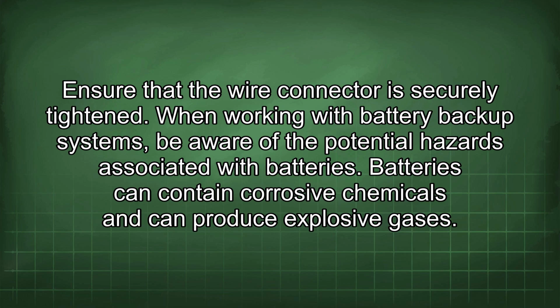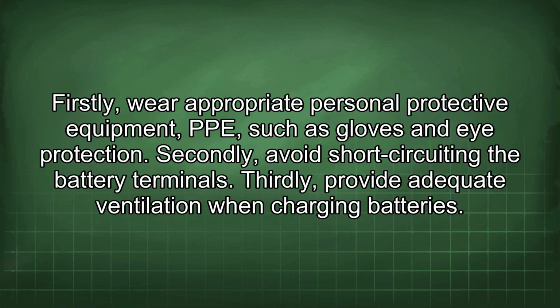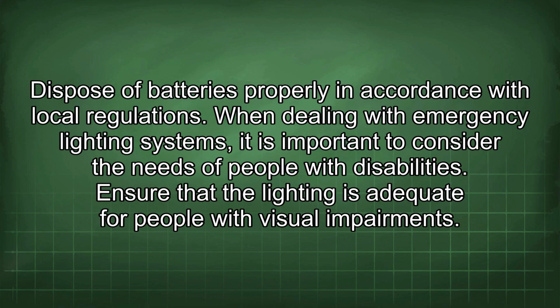When working with battery backup systems, be aware of the potential hazards associated with batteries. Batteries can contain corrosive chemicals and can produce explosive gases. Firstly, wear appropriate personal protective equipment, PPE, such as gloves and eye protection. Secondly, avoid short-circuiting the battery terminals. Thirdly, provide adequate ventilation when charging batteries. Dispose of batteries properly in accordance with local regulations.